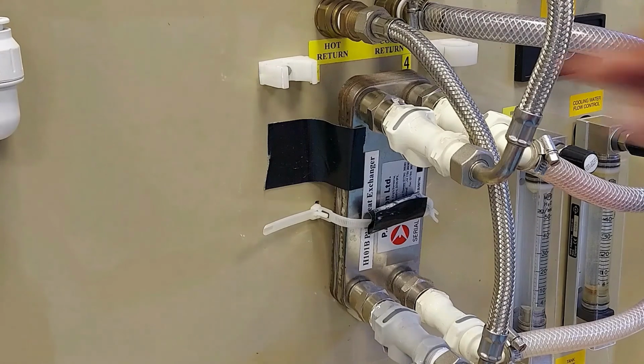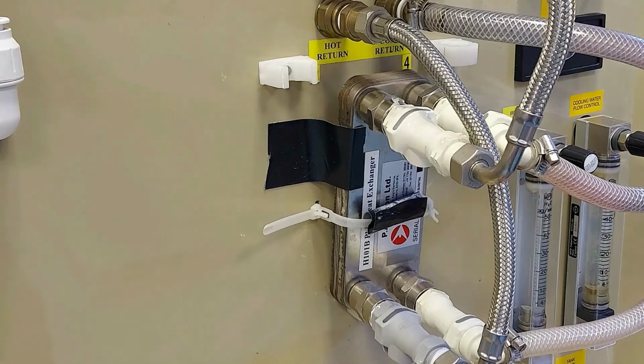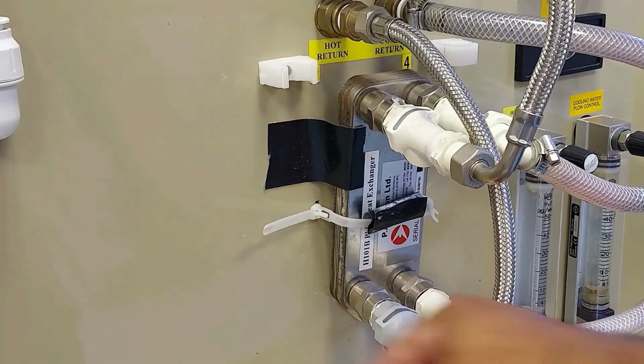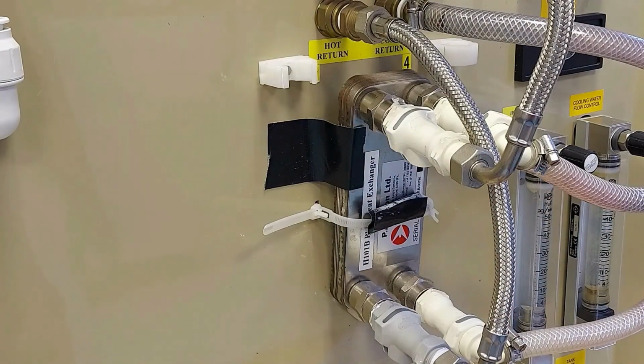A plate heat exchanger uses metal plates to transfer heat between two fluids. It consists of a series of parallel plates placed one above the other so as to allow the formation of a series of channels for the fluids to flow between them. Basically, the fluids are flowing against each other but separated by the metal plate. The inlet and outlet holes at the top and bottom corners of the plate allow hot and cold fluids through, so that a plate is always in contact on one side with the hot fluid and on the other side with the cold fluid.